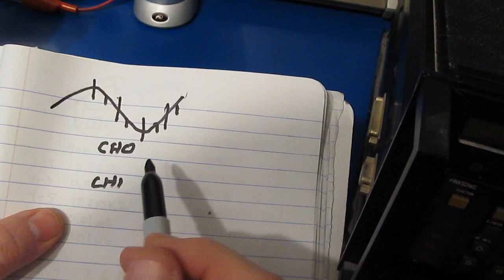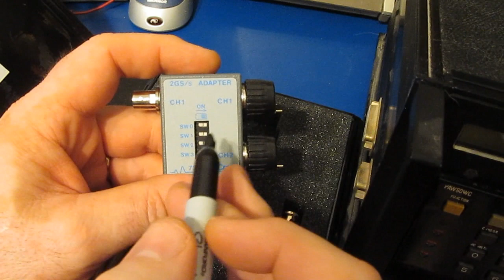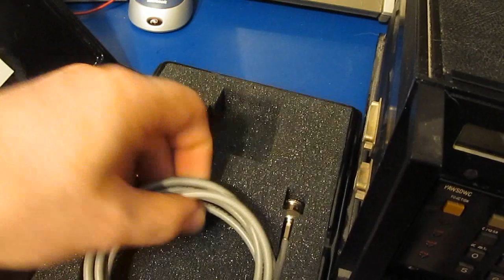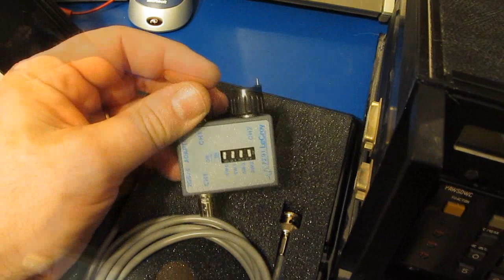So the old LeCroy 7200 supports this mode. There's an external adapter. This is what it looks like. So this is just a delay line, and it's causing, in this case, a 500 picosecond delay between the 2 channels. And then these dip switches add different lengths to that delay line. There's a resistor built up into the connectors, and that tells the oscilloscope that this is attached, and that'll cause the software to stitch the waveforms back together. And you can see there's a little cable here with an SMA. This goes to your load that you're trying to measure.